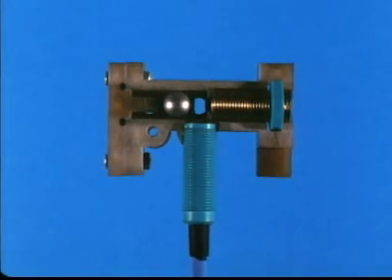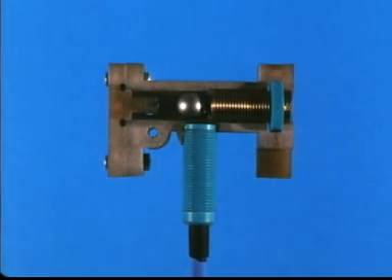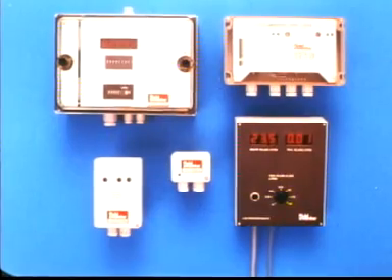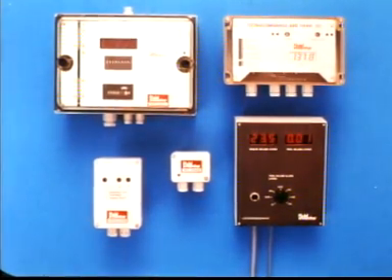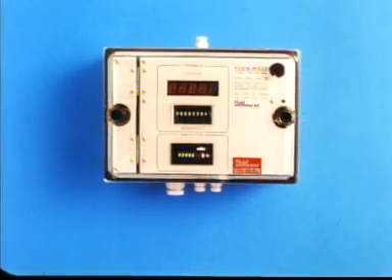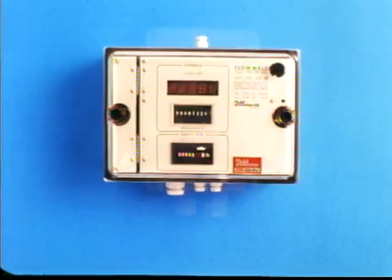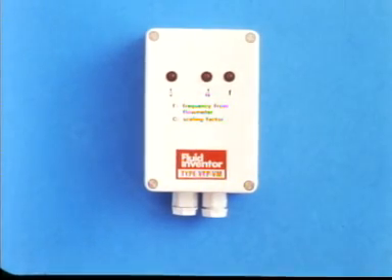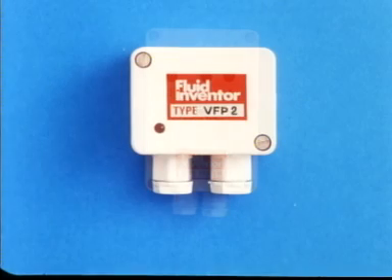The ball, which senses the pressure changes in the fluid passages and which applies the electronic pulses, is located outside the Fluidistor itself. The electronic pulses can then be converted into a pulsed or analog output in a signal converter. Fluid Inventor has developed a complete range of signal converters, which are also available in explosion-proof enclosures for hazardous environments. The converted signals are applied to a recorder, computer, direct reading instrument, etc., but can also be employed for direct control of valves and for use in control systems.